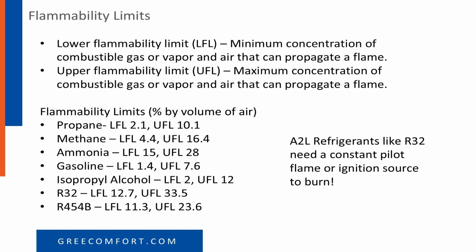Propane has a lower flammability limit of 2.1 and an upper flammability limit of 10.1. Methane, natural gas, LFL 4.4, UFL 16.4. Ammonia, lower limit of 15, upper limit of 28.